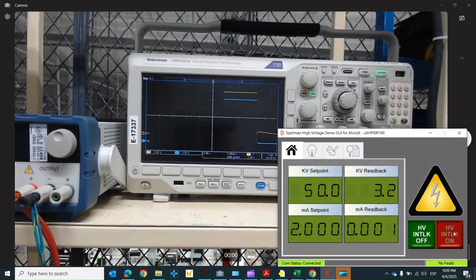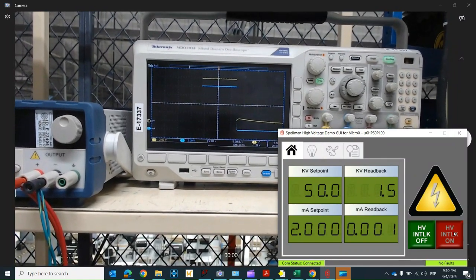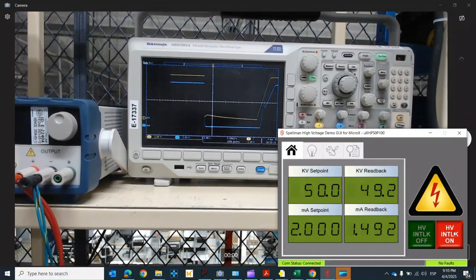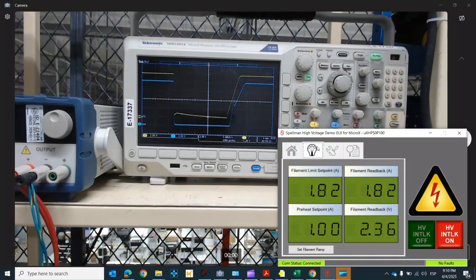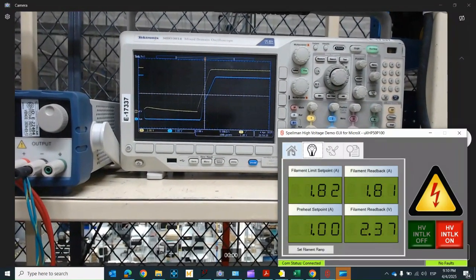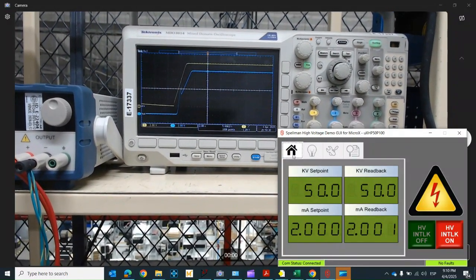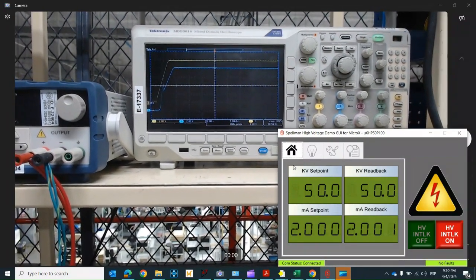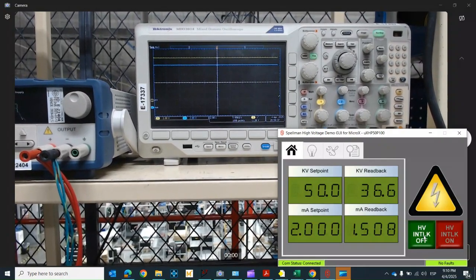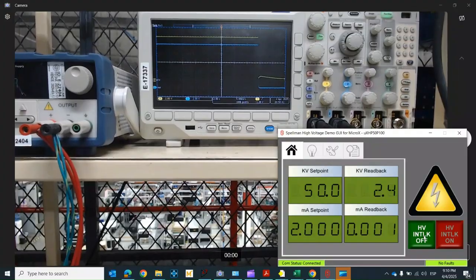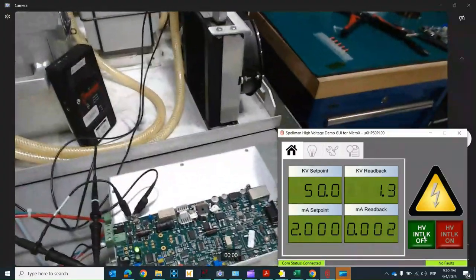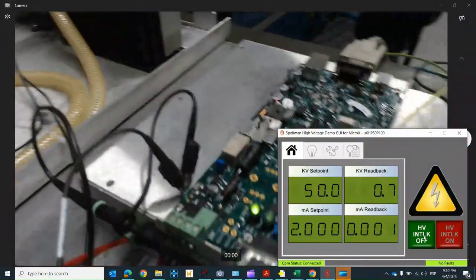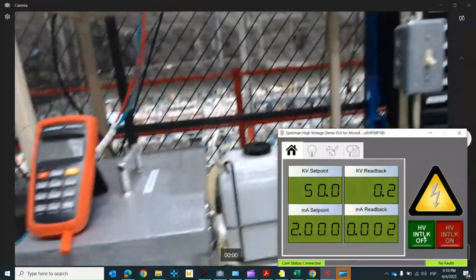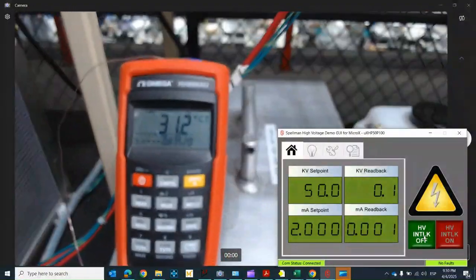Tube will continue to be left operating to look for any abnormalities. Interlock will also be opened and closed to confirm filament and emission current ramp at approximately the same time and oscillations do not occur. Once X-ray tube temperature has reached 30 degrees Celsius, interlock will be opened to shut down operation. Interlock status LED in the multiplier will be reviewed, and multiplier and control temperature values from the diagnostic screen will be recorded in the test datasheet.